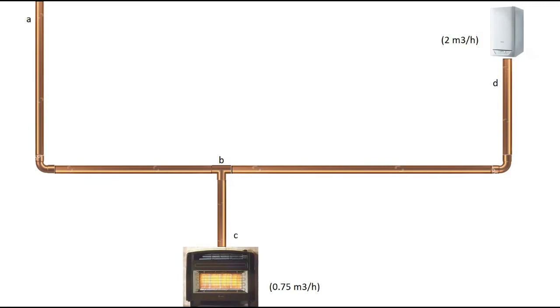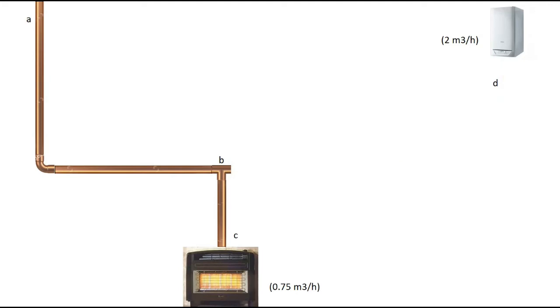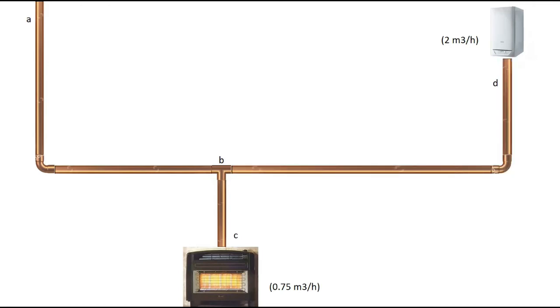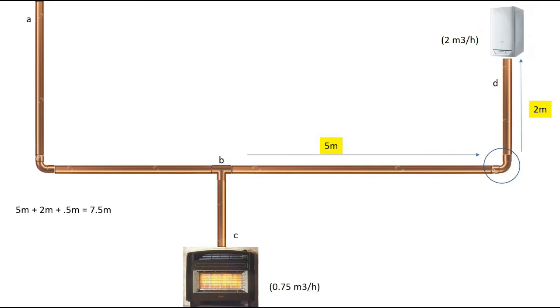That leaves us with the last part of our puzzle, which is B to D. If we take it away, you can clearly see that without that pipe the fire still gets gas, so that pipe is only carrying gas to supply the boiler. The boiler needs two meters cubed per hour of gas. We're saying it's five meters long, then after the bend there's two meters more of pipe — seven meters total — but it's got an elbow in it, and for an elbow you add 0.5 of a meter. So the maths works out as five plus two plus 0.5 equals 7.5 meters.